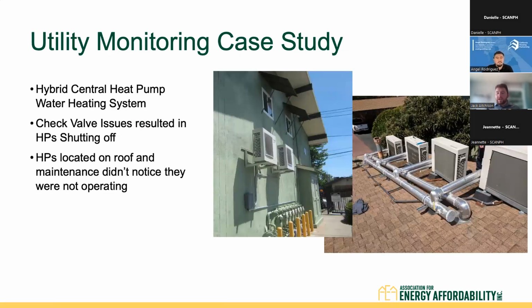So, utility monitoring case study. This is an example of when utility monitoring went right, and we were able to find a problem, address it, and reduce utility bills. We had a project that did a hybrid central heat pump water heating system. Essentially, that means we did not have enough electrical capacity to have heat pump water heaters cover the full domestic hot water load at the site. So instead we did heat pump water heaters and a gas water heater as a backup and top-off heater in case the heat pumps can't meet the load.